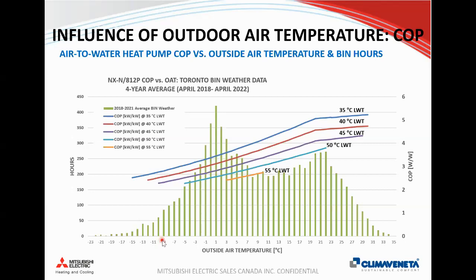Even if you look at a climate like Calgary, they still spend about 49% of the year between -10 and +10. So when it comes to using these heat pumps, it's not all or nothing. We just need to use the heat pump when that makes sense and use auxiliary gas when that's required. The second thing this chart is showing us is our COP according to ambient temperatures for different supply water temperatures. The key point here is this is also telling us our operating envelope.